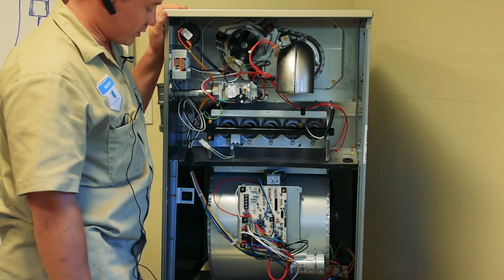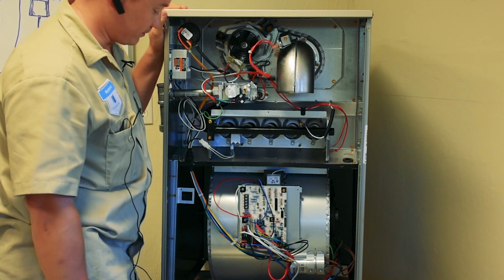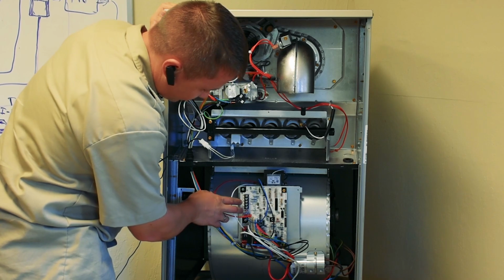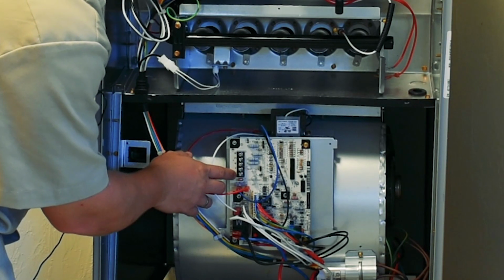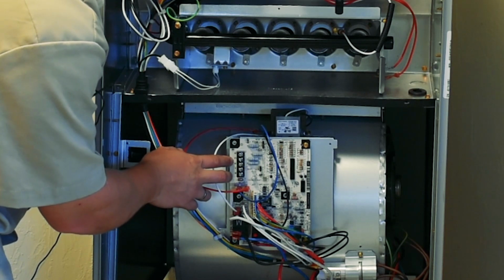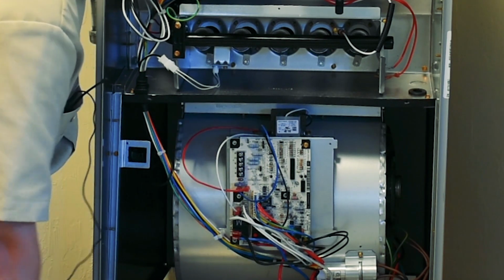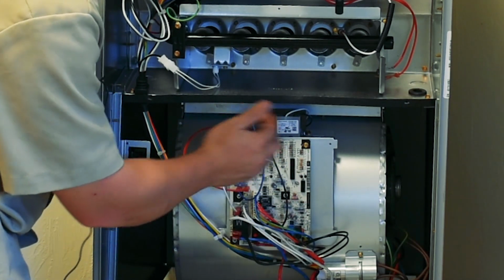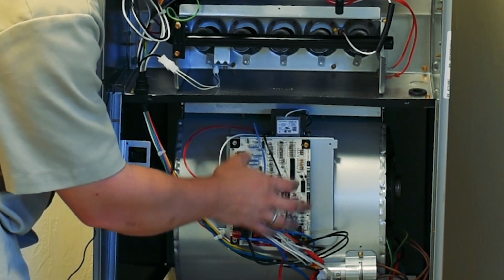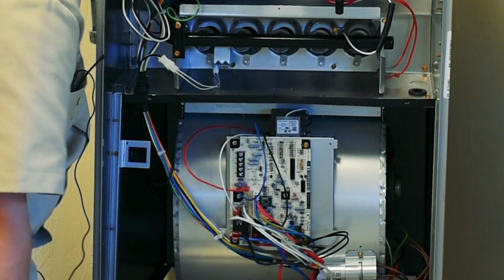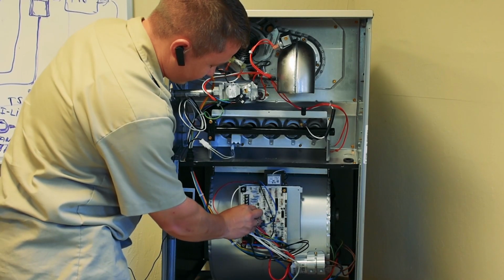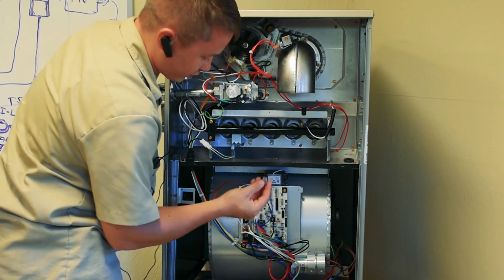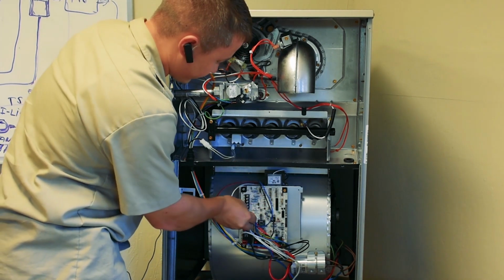When you turn on the thermostat and require heat, it bypasses 2 terminals, W and R. Here is the incoming for the R terminal, 24 volts AC. Like I said, the control board has 2 circuits, low voltage and high voltage, 120 volts and 24 volts. For the 24 volts circuit, the control board also has a fuse for 3 amperes.